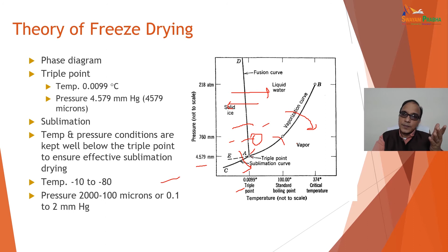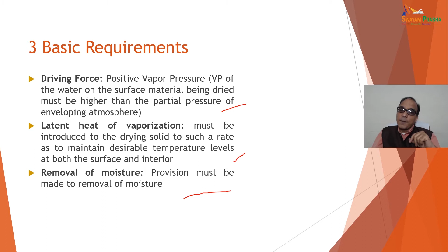What are the three basic requirements for freeze drying? Number one, driving force. Number two, latent heat of vaporization. And number three, removal of moisture. The driving force must be a positive vapor pressure: the vapor pressure of the water on the surface of the material being dried must be higher than the partial pressure of the enveloping atmosphere. The second condition is that the latent heat of vaporization must be introduced to the drying solid at such a rate as to maintain desirable temperature levels at both the surface and the interior. And the third basic requirement is that there must be provision for removal of moisture at the time of drying, at the time of sublimation. So positive driving force, latent heat of vaporization must be introduced, and third, removal of moisture provision must be made. These are the three basic requirements for freeze drying.